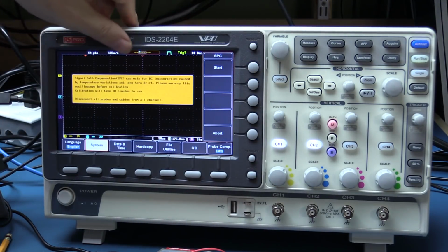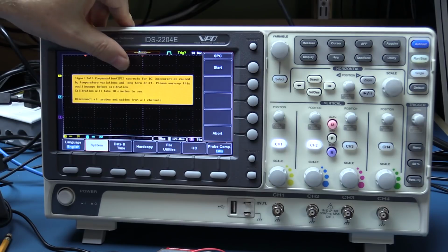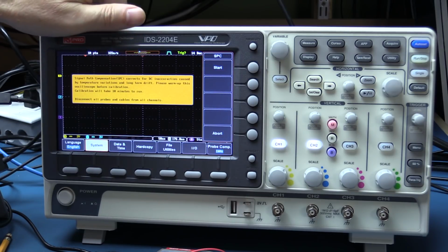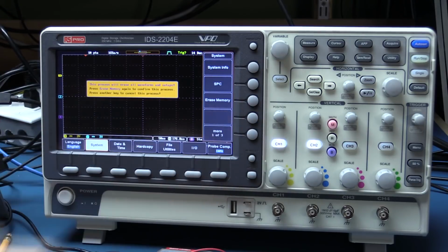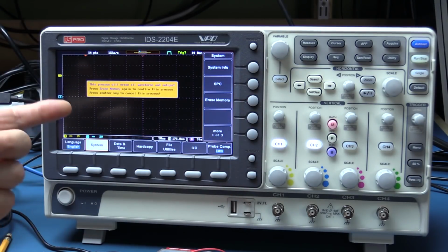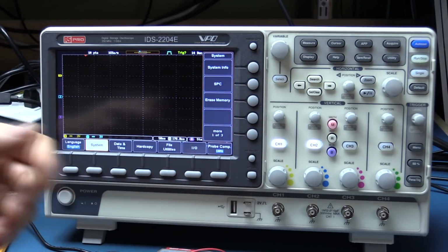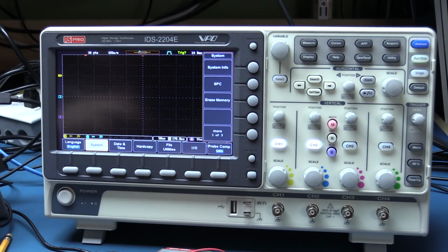SPC, signal path compensation. This is a calibration that you can do. It will take about 10 minutes to run, so I'm not going to do that right now. You can erase memory. I'm not going to do that either, because I've just got this set up for a few things. But if you needed to completely erase the memory from waveforms and various other things, maybe you're going to lend this scope to somewhere else and you've got some proprietary waveforms that have been captured, then you can do an easy erase of the entire scope, set it back to factory conditions effectively.